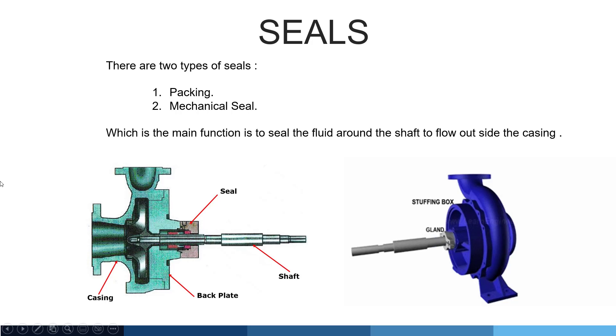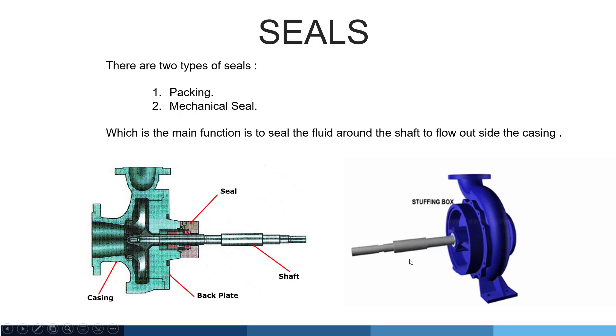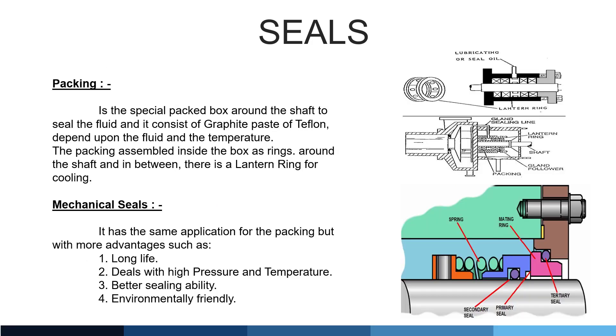Seals. There are two types of seals: packing and mechanical seals. Their main function is to seal the fluid around the shaft to prevent flow outside the casing. Packing is a special packed box around the shaft consisting of graphite-based or Teflon material, depending on the fluid and temperature. The packing is assembled inside the box as rings around the shaft, with a lantern ring in between for cooling. Mechanical seals have the same application as packing but with more advantages such as long life, ability to deal with high pressure and temperature, better sealing ability, and environmental friendliness.